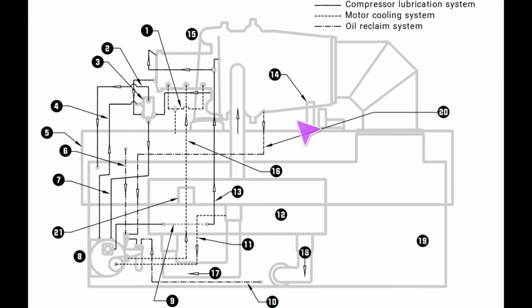Let's talk now about oil return and oil management. There are three points of oil return that this machine goes through, and they reference these as eductors. Again, I'm not an expert on the eductor theory or design. I just know that it exists, and I try my best to work with it. Regardless, the first stage eductor is right here, coming right off the bottom of the sump. Its job is to pull any oil that collects in this portion of the system. Oil is heavy, so it's going to fall towards the bottom. Any oil that is allowed to make it to this point, this return line's job is to draw that oil back into the sump.